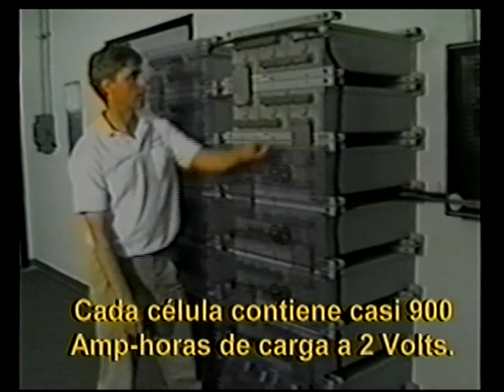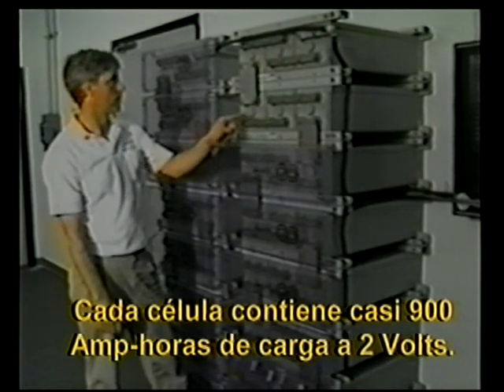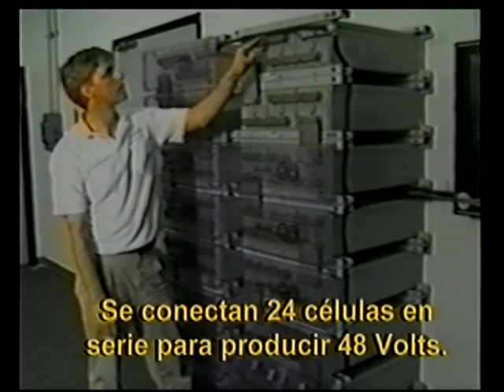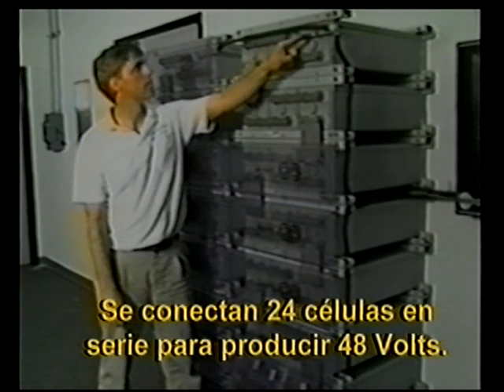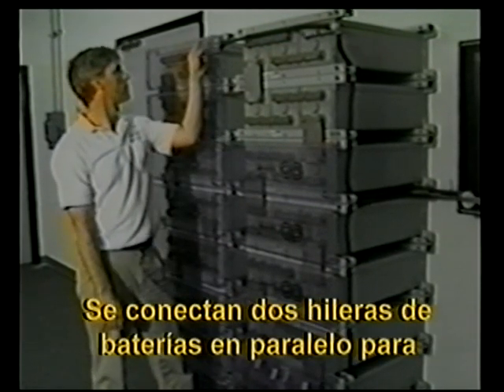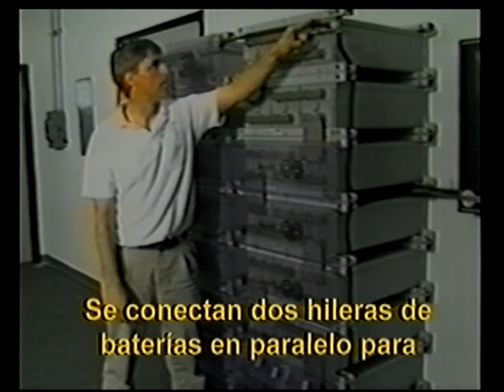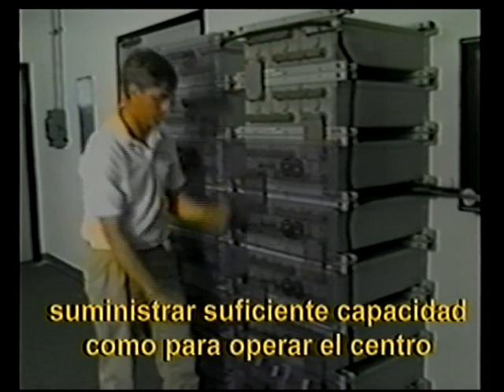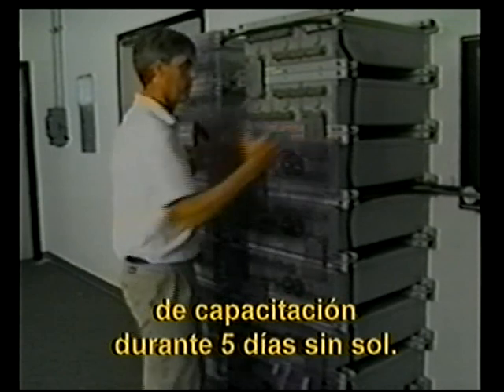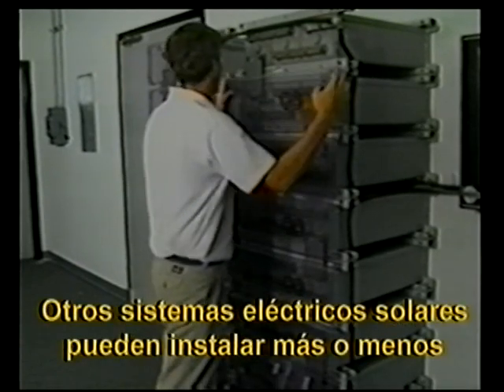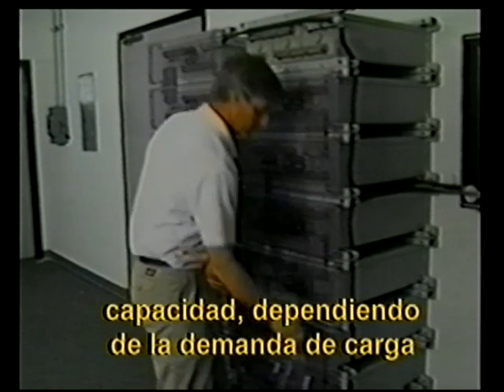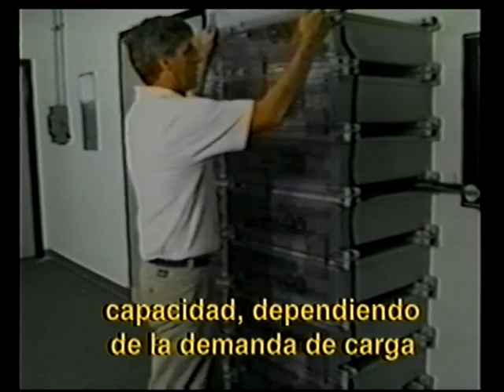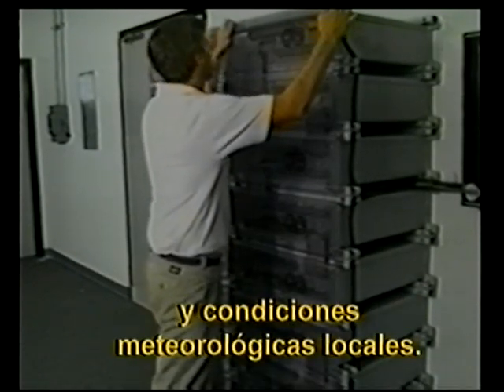Each cell contains almost 900 amp-hours of charge at 2 volts. 24 cells are connected in series to produce 48 volts. 2 battery strings are connected in parallel to provide enough capacity to operate the training center for 5 days without any sun. Other solar electric systems could install less or more capacity depending on the load demand and local weather conditions.